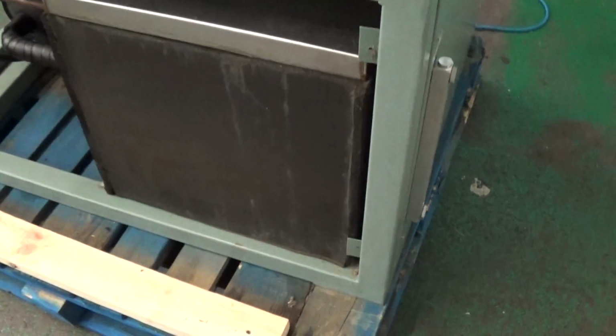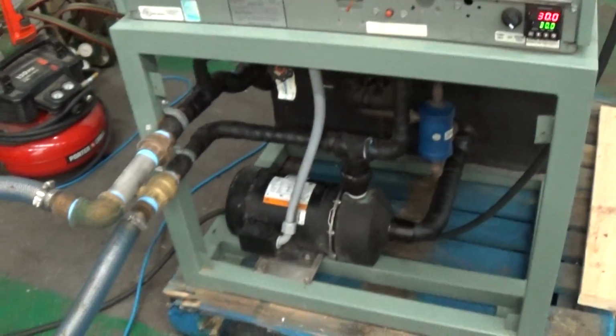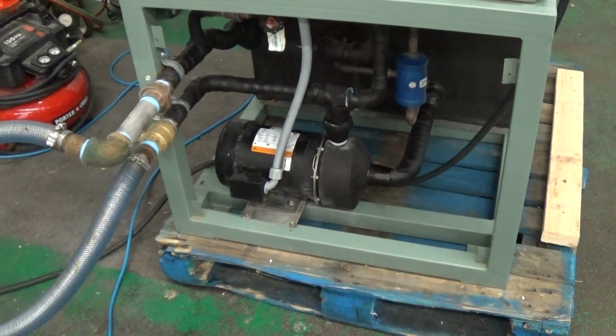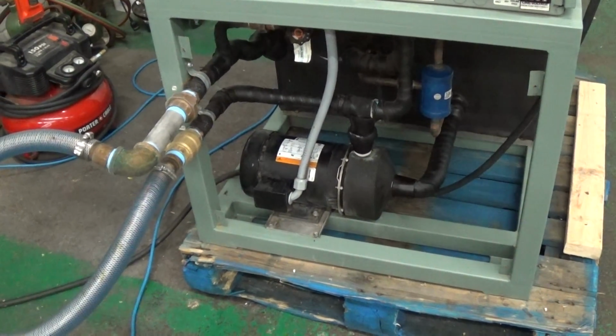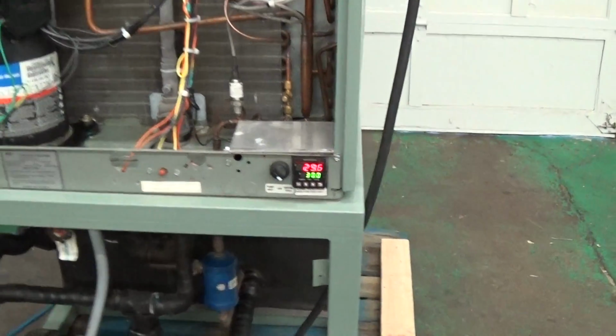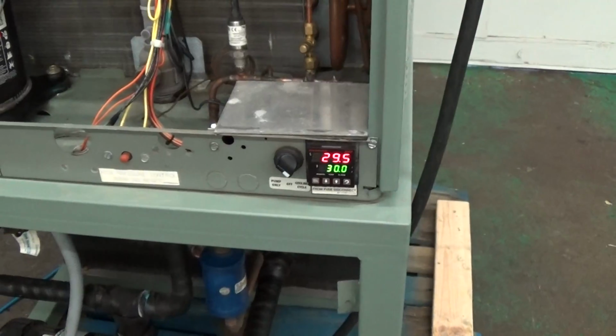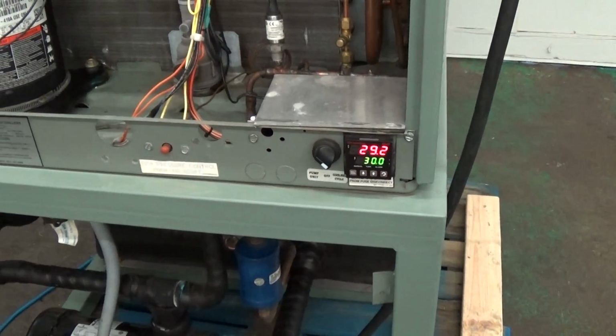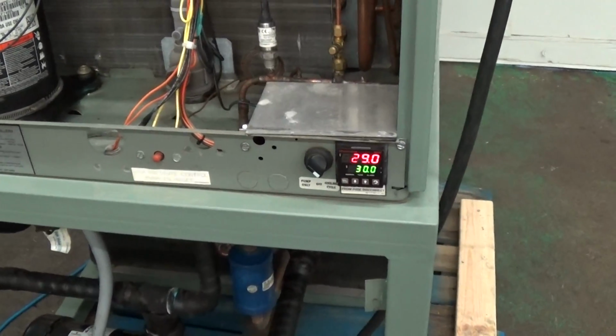The lighting's not super great here, but you have a stainless cover. Tough to see in there, but the brazed plate exchanger does sit in the bath of the glycol, which is a preferred way to do it as far as insulation qualities, and also in the unlikely event you run too low of a glycol solution, that helps prevent quick freeze-ups inside. So we're stabilized at right about 30 right now. It'll take a while for it to get back up with no load before the chiller turns on again.